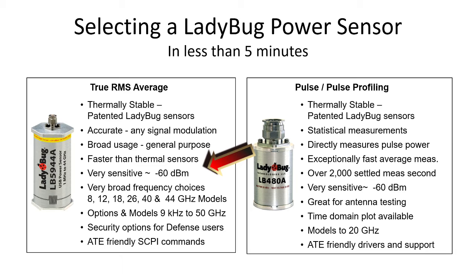They're much faster than thermal sensors, and they're much more sensitive than thermal sensors. You can measure down to minus 60 dBm up to plus 26 dBm with one of these sensors. We offer them in a broad selection of frequency coverages, 1 megahertz to 8 gigahertz, 12, 18, 26, 40, and 44 gigahertz in one sensor. You can also get optional 9 kilohertz capability, so you can measure 9 kilohertz to 44 gigahertz without changing a sensor. This is great for source calibration.